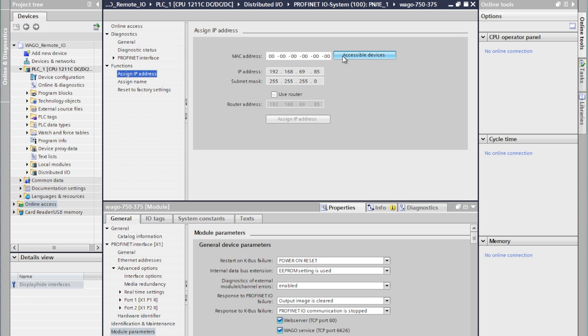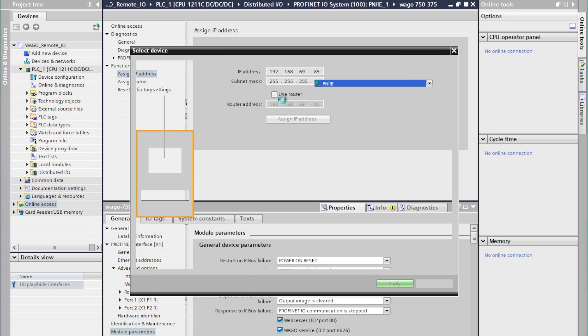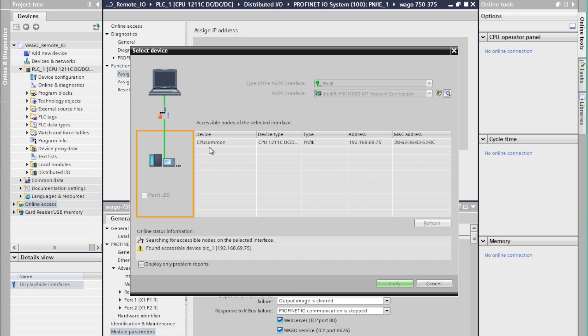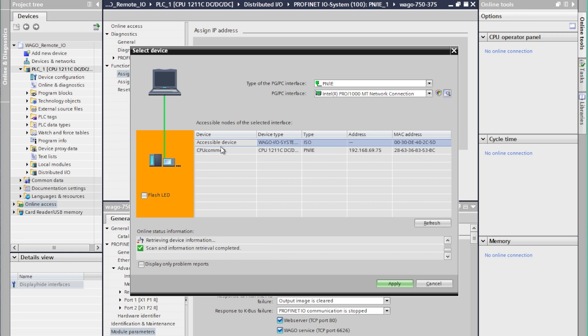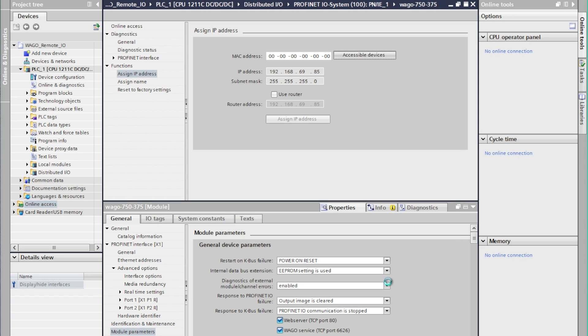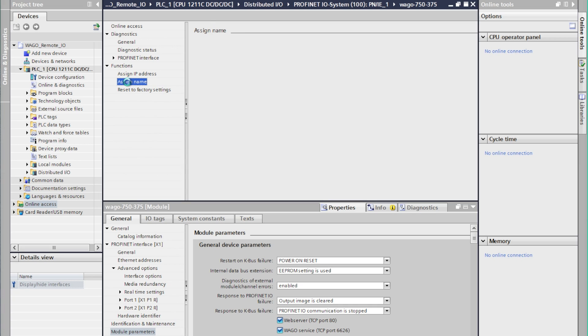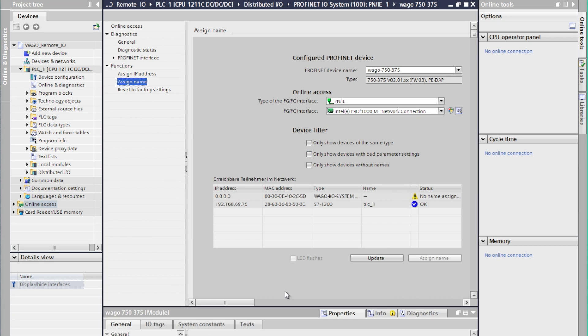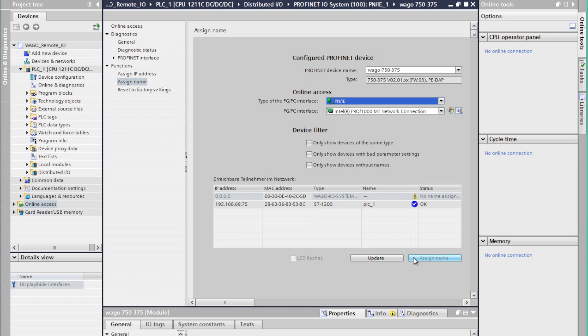So following the same steps we'll go to online and diagnostics, search the system for the coupler and we will select it and assign the IP address and the name in the same fashion we did as the PLC. We probably could skip assigning the IP address however it's good to be able to establish outside communications with the controller to verify that everything is online. And here we've assigned the name as well.